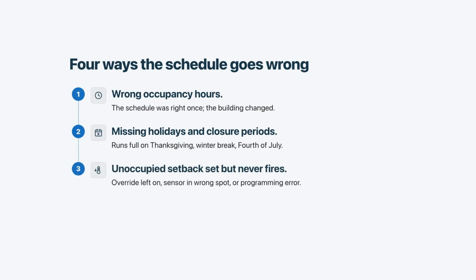Number 3 is nighttime setback failures. A setback is supposed to drop the target temperature during unoccupied hours so the system does less work. The setback's programmed, but the system isn't actually hitting the target. Common reasons are a zone override that was maybe set for a late event and never cleared, or a sensor placed in a drafty hallway that fools the controller, or a software bug that never got a ticket.